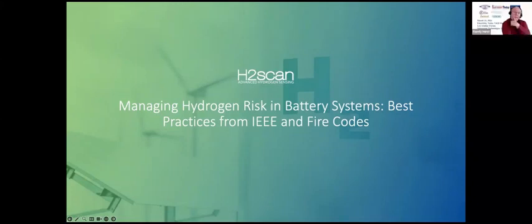What are the best practices for ventilating spaces containing battery systems? Ventilation basically is using IEEE 1635. Yeah. And understanding the level of ventilation you need. So you're going to select a gas purge fan that has the airflow, the air exchange rate, possible to handle those worst case scenarios. And that ventilation system must be explosion proof, and also, like I said, it can be tied into the detection system, which is the preferred method.